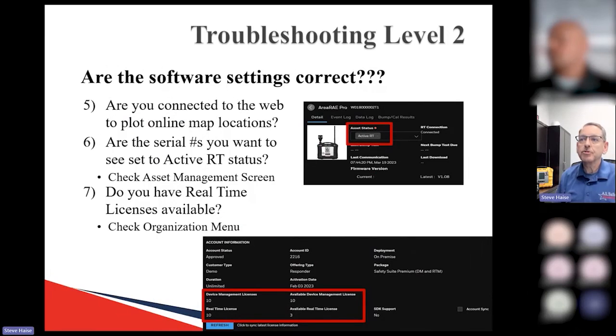Finally, troubleshooting level 2, step 5: are you connected to the web to plot online maps and locations? We're using Google Maps with the GPS coordinates captured by the card in the AreaRAE to plot that on a map, so you'll want to be connected to the internet so that can populate. To confirm, use the toolbar on the left to navigate to the Asset Management tab and confirm each instrument serial number is set to active RT.